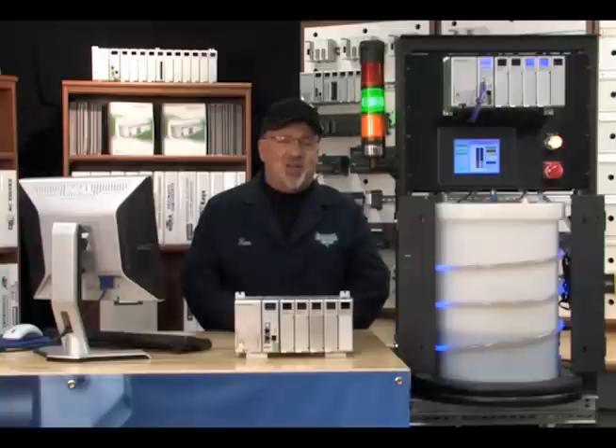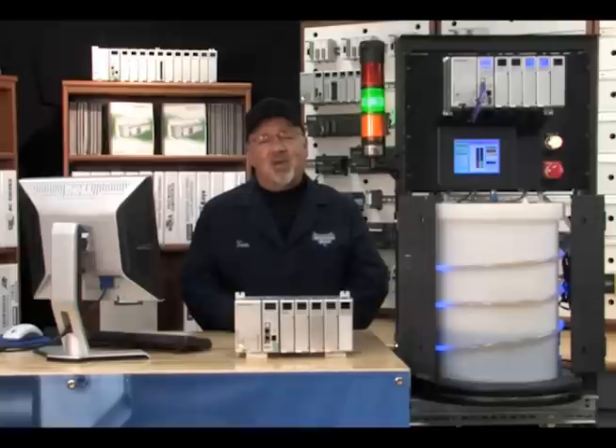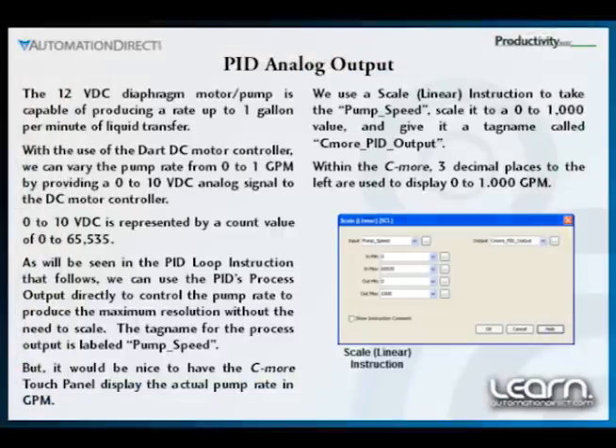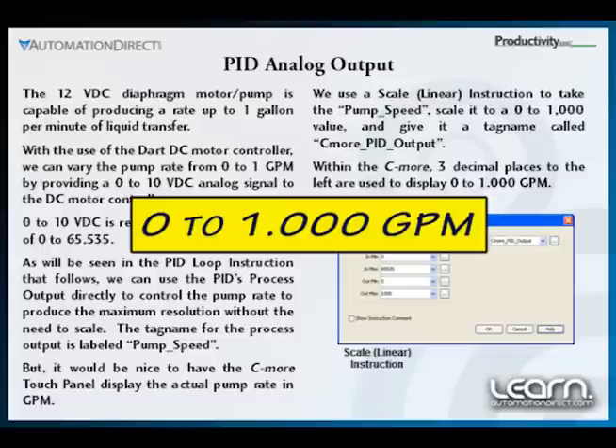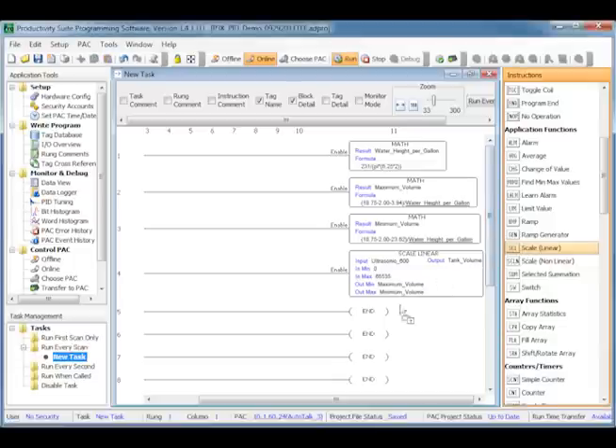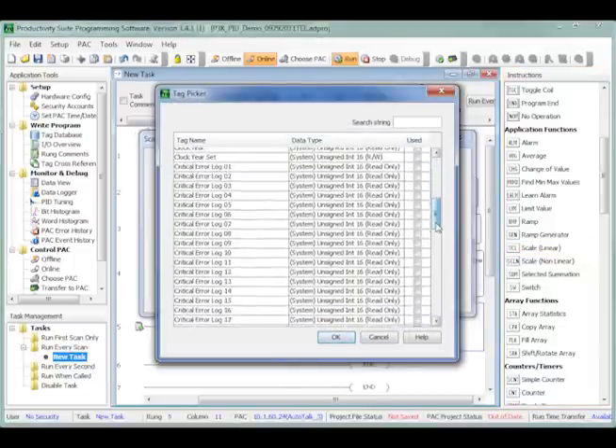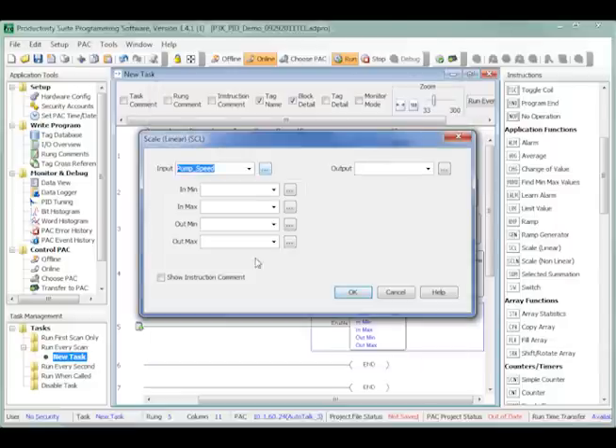It would be nice to have our C-more touch panel display the actual diaphragm pump rate in gallons per minute. This is another easy task that makes use of our scale linear instruction. Our goal is to create a value of 0 to 1,000 based on the pump speed value of 0 to 65,535 at any given instant. In the C-more touch panel we will display the result showing 0 to 1.000 gallons per minute by using a decimal point three places to the left. Drag and drop the scale instruction into the next end coil, then select the tag name pump_speed in the scale instruction input parameter. For the in min parameter enter 0 and the in max will be 65,535.